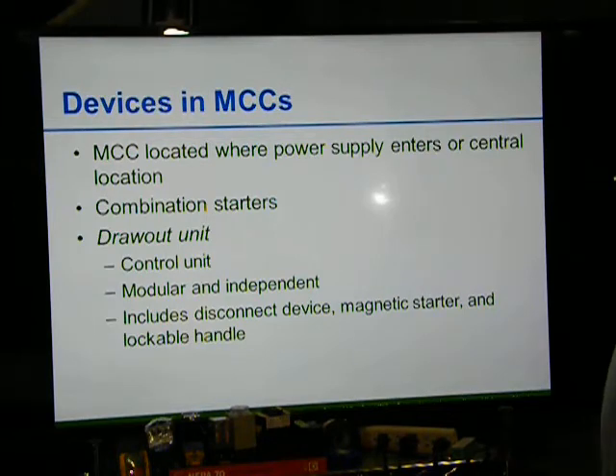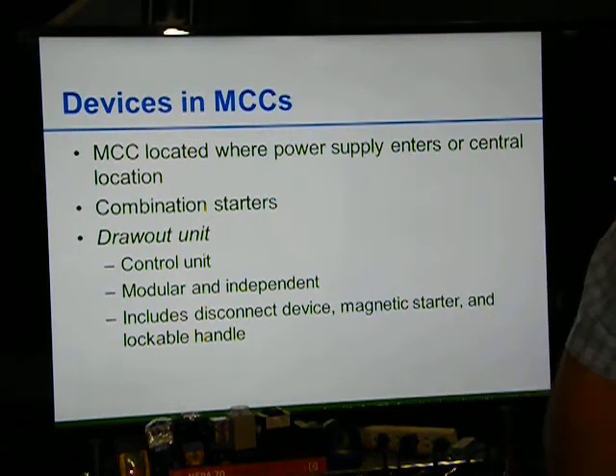MCC located with power supply, combination starters. The combination starter is normally used with the motor control center. The MCC can also house feeder taps for remote equipment other than motors, such as heaters and lighting panels. Each control unit, called the draw out unit, is a module independent from the other modules.